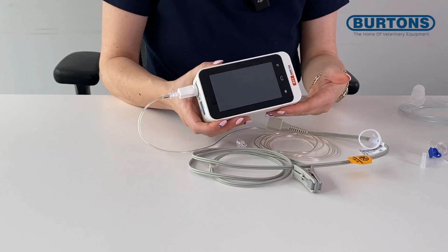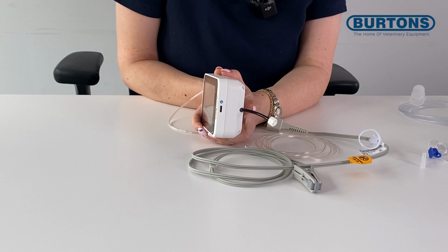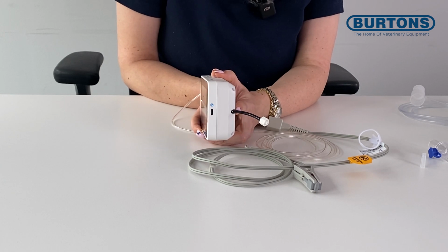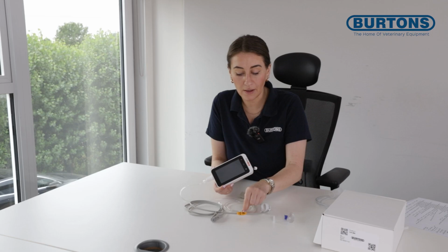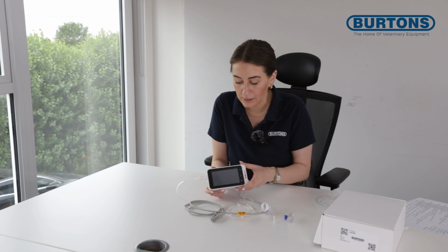The other aspect just to touch on is the exhaust port. As the machine pulls in the sample of the breath from the patient, we use that portion of the breath to analyse the CO2, but any trace elements of inhalational gas are removed to your scavenging system so that we're not polluting room air with trace elements of sevoflurane or isoflurane, depending on what you're using.